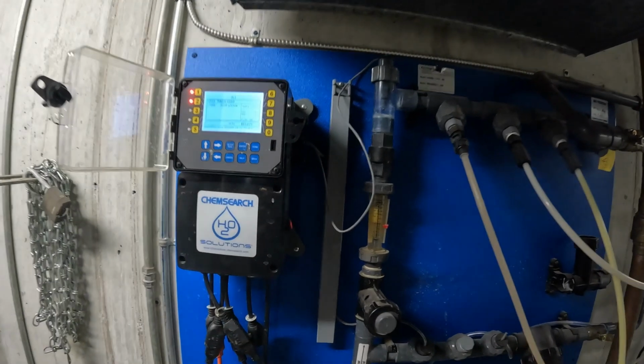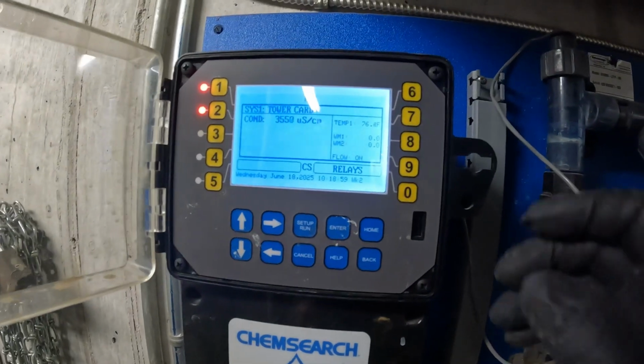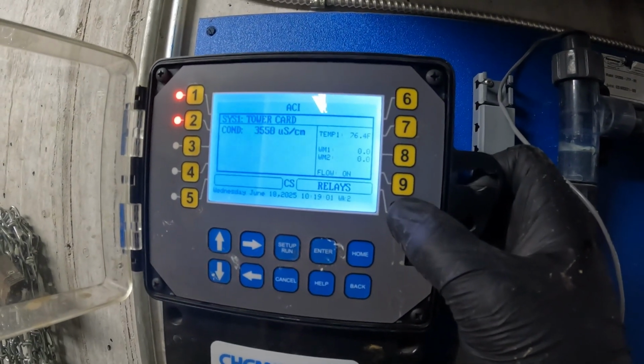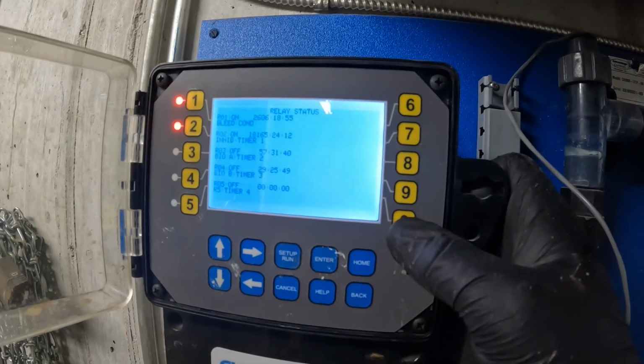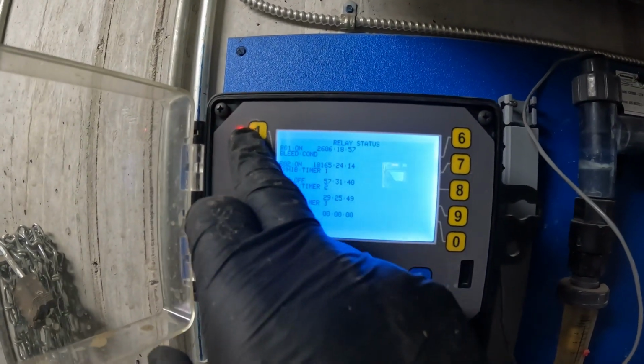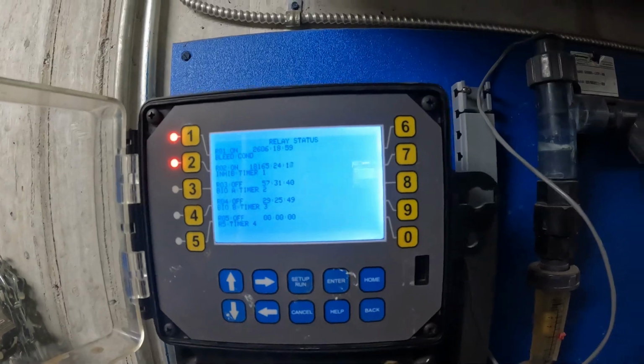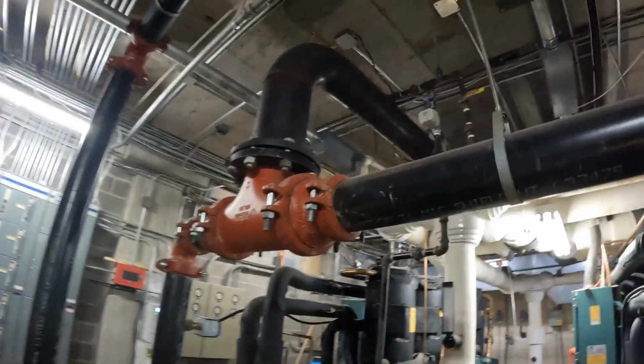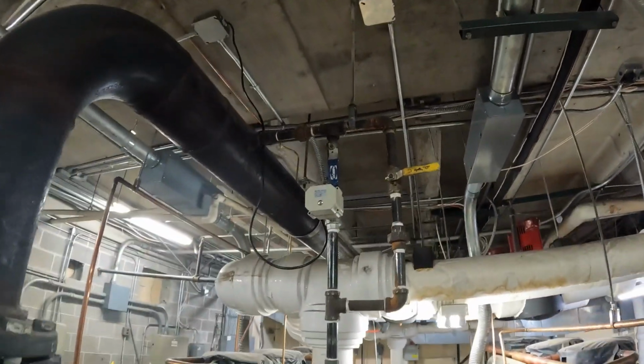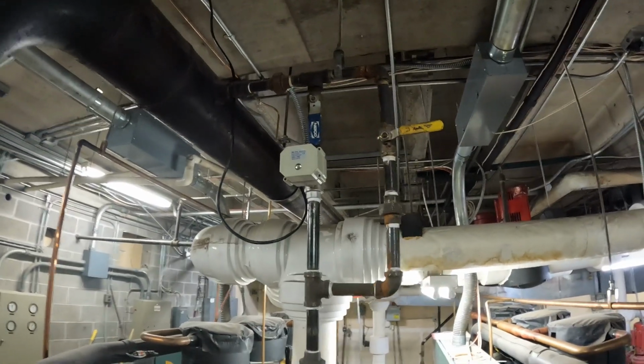Now let's take a closer look at the controller and test the relays. Each controller can be different, so be sure to watch the controller videos that we have on our ChemsearchFE YouTube page. Relay 1 is usually the bleed for the tower. Once activated, if it is accessible, you can check that the solenoid opens and the tower starts to bleed.